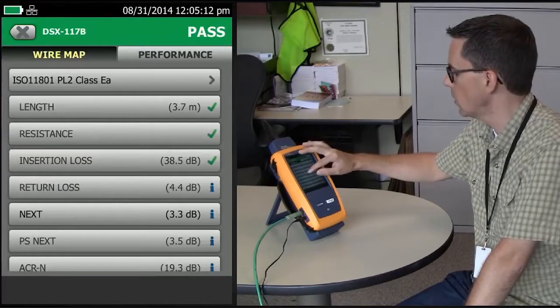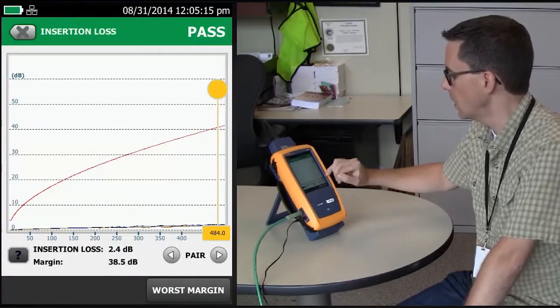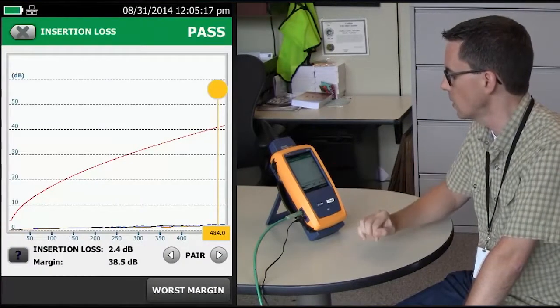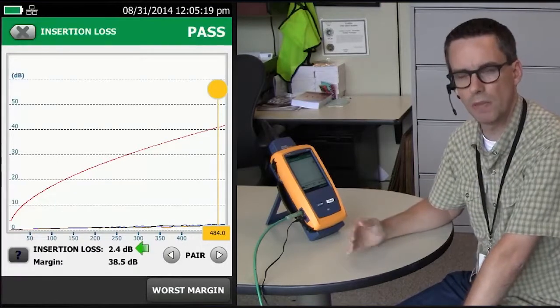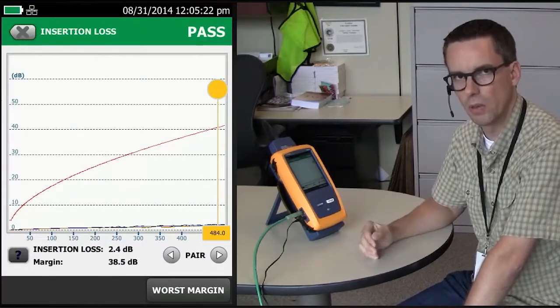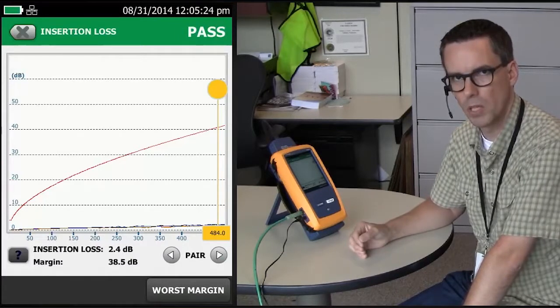When we look at this near-end crosstalk, we see that the entire limit line is black, so the entire measurement is ignored. If we go and look at the insertion loss, we can see here that it reported the worst case as 2.4 dB, not even close to 4 dB, so it's ignoring all of the crosstalk measurements.